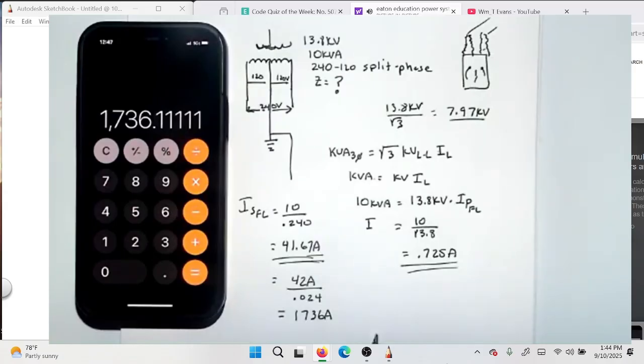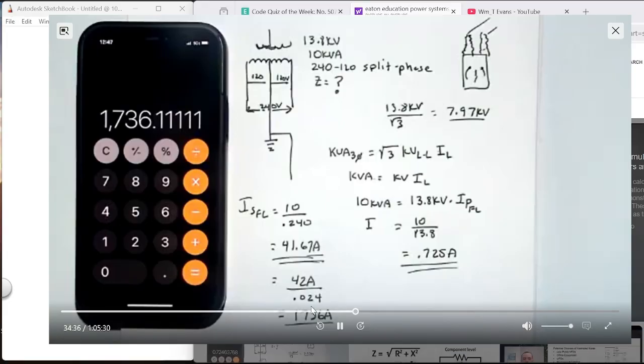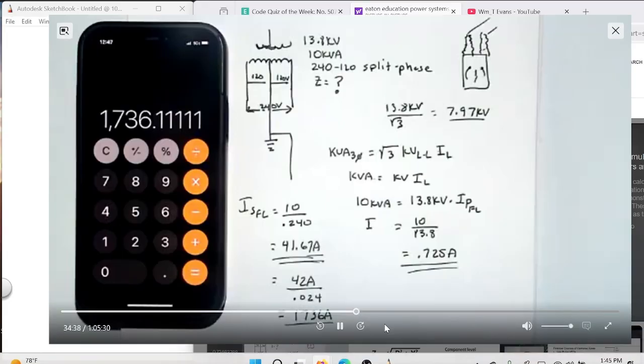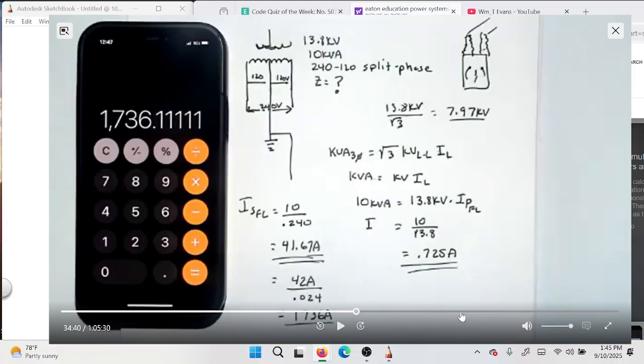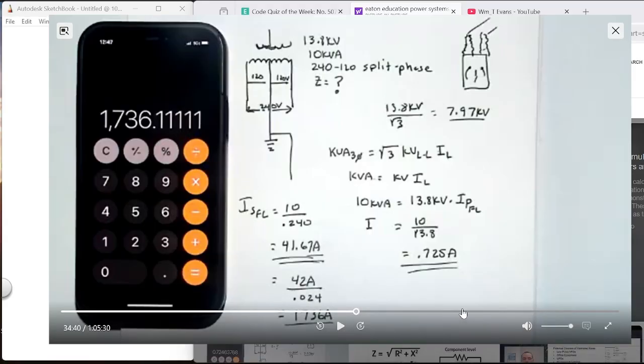Typically in our homes, we're using 10 kA breakers, so this is well within that range. That's the fault current right there in a home. That'll get you an arc and a spark. We don't really have it for single phase pole mounted, but he has the nameplate, so as long as you keep it between like 2 and 3%.